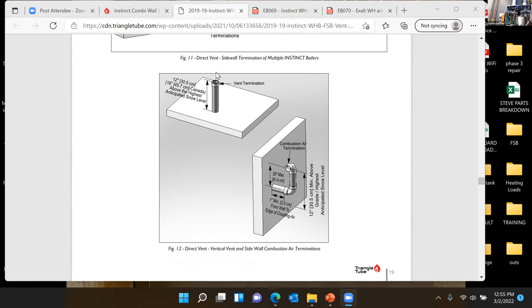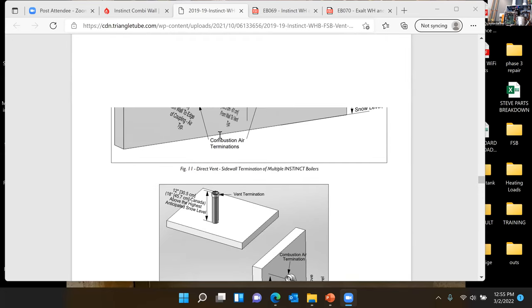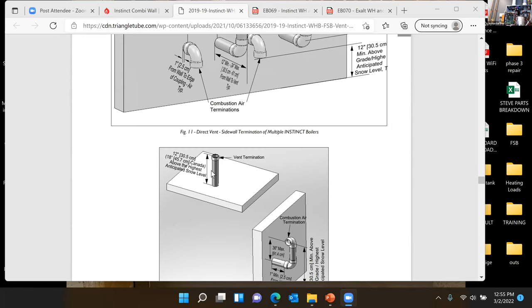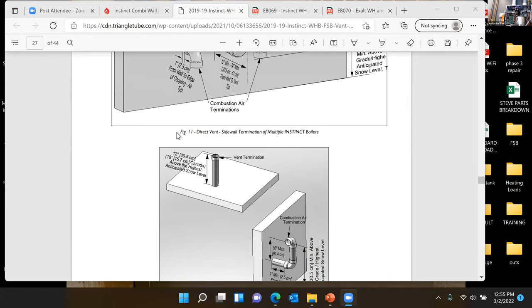If you're going to bring in fresh air intake, again, we need it 90 down, facing down, to prevent any water coming through here. And if this is our air intake, we do need a 90 on here, or we can just come out with a 90 and drop it straight down right here. Through the roof applications are great, because we get a lot of that rainwater that will come back down through and help keep our condensate trap clean. So that's one advantage of going through the roof, is having that rainwater come down and help clean out that trap a little bit and get some of that gunk out of there.